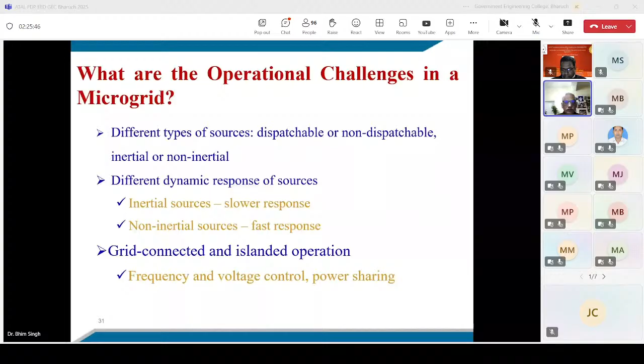There are problems in synchronization of distributed generation, inrush current from transformers and induction motor-like generators, three-phase unbalance from single-phase loads and single-phase photovoltaic generation, and recent trends introducing many DC loads which are more efficient, requiring AC-DC or DC-DC converters. There's also the introduction of distributed generation with DC output like PV, fuel cells, wind turbines, micro turbines, and gas engines, along with the need for higher quality power.